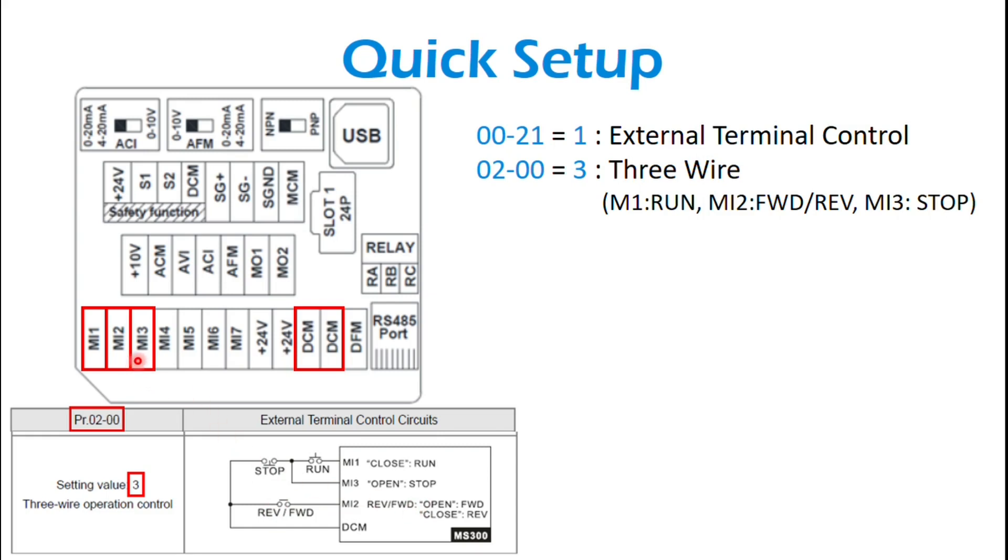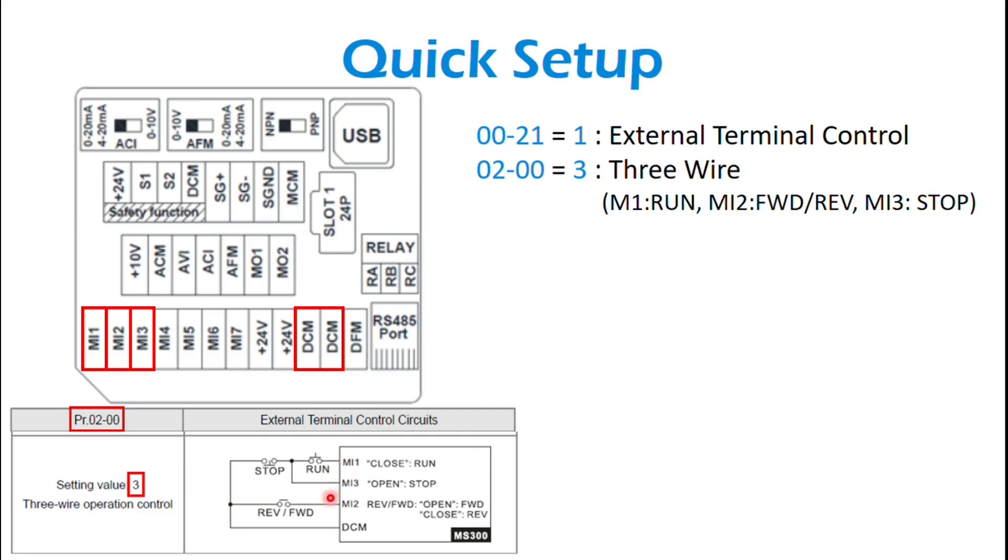And then MI3 is your stop. So it's a normally closed dry contact to your MI3 for stop. And when you set 0200 to 3, these functions kind of automatically get set. So these are the only two parameters you need to set for that.